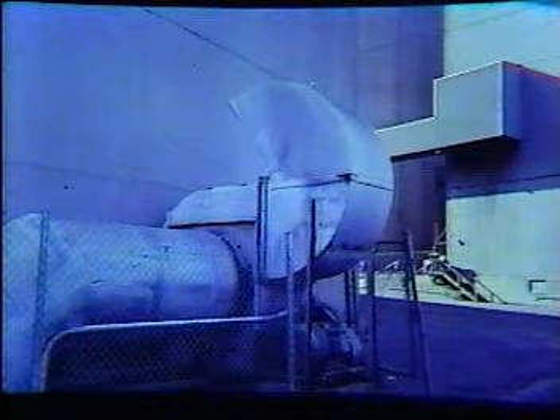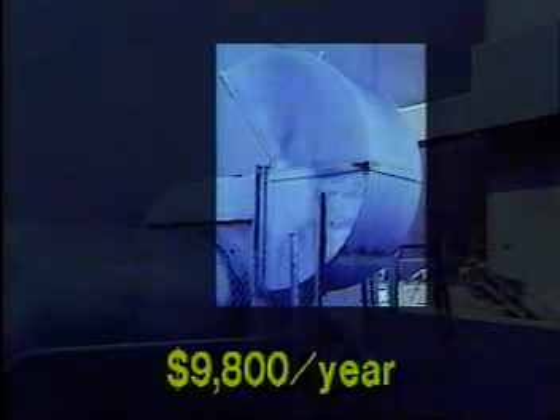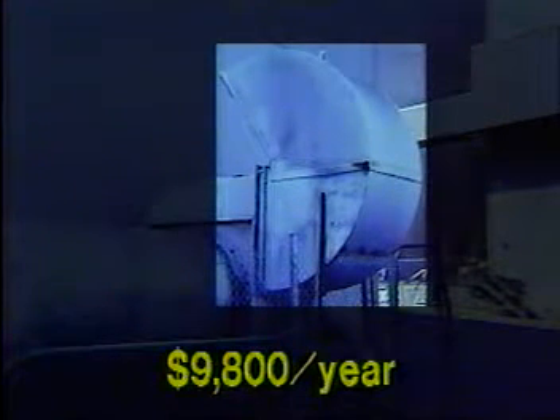Example: a 49-inch fan was right for the job, but it was installed with an abrupt elbow at the outlet. The result? A $9,800 increase in the annual energy bill due to the increased fan speed required to overcome this system effect. Fans can use more electricity than all of the other system equipment in the plant or building combined.